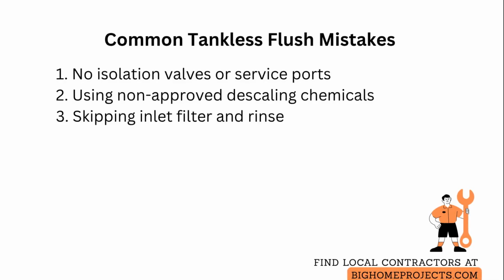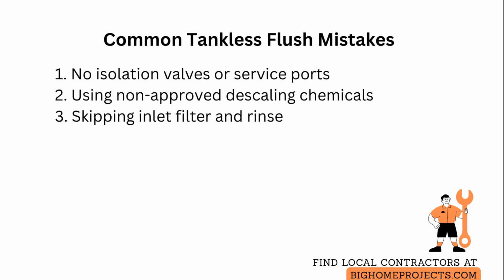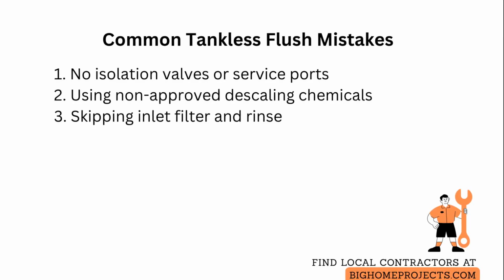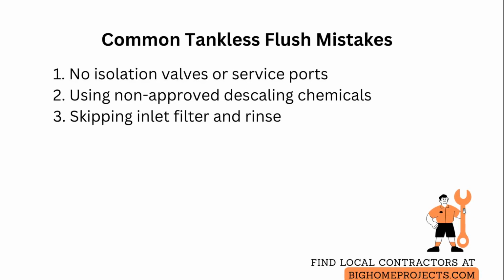The third mistake is skipping the inlet filter and not rinsing long enough, which leaves grit and cleaner in the heat exchanger and triggers flow errors. Pull and clean the screen and do a clear water rinse for several minutes until the water runs clean.